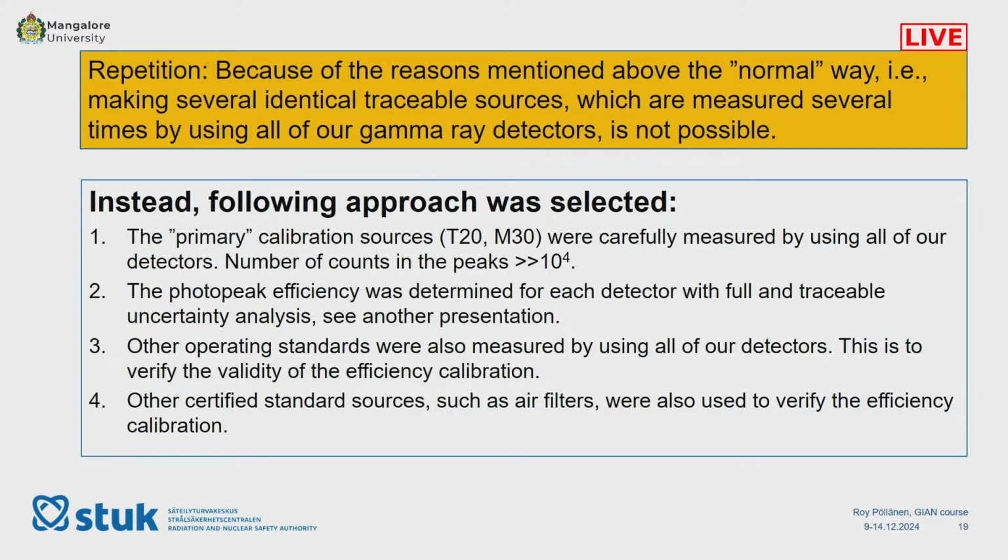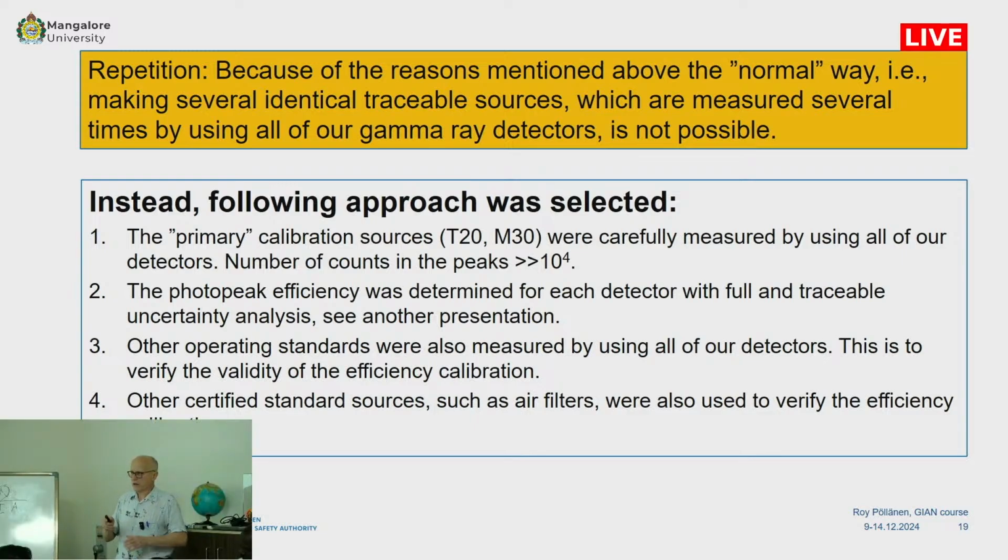Because we are using this FTRAN software, we have to do it this way just to verify that the basic calibration is okay, and also the efficiency transfer calculation is okay. And once we have shown that it is okay for the certified reference samples, then in normal samples we can rely on the calibration.